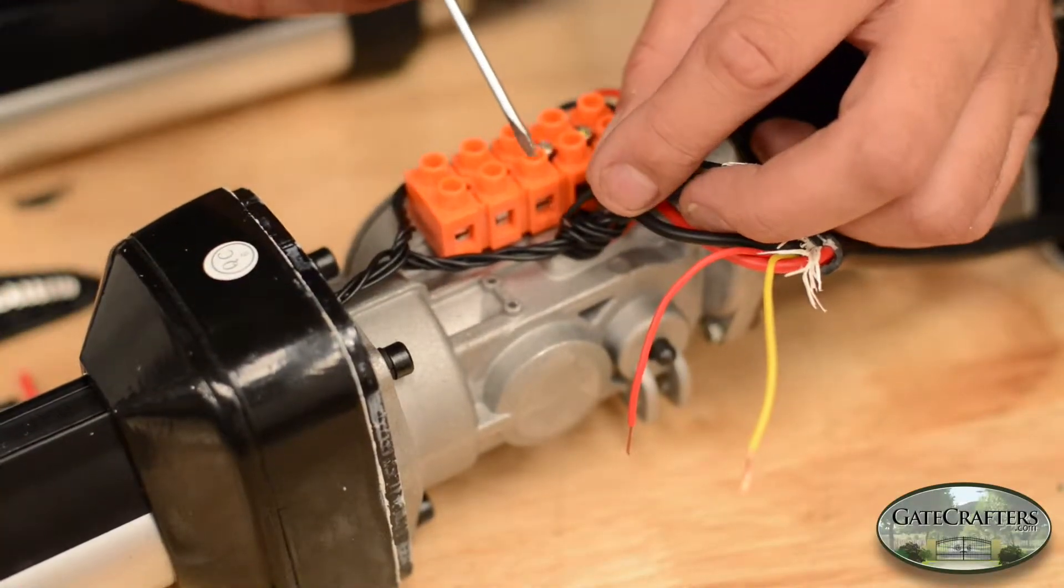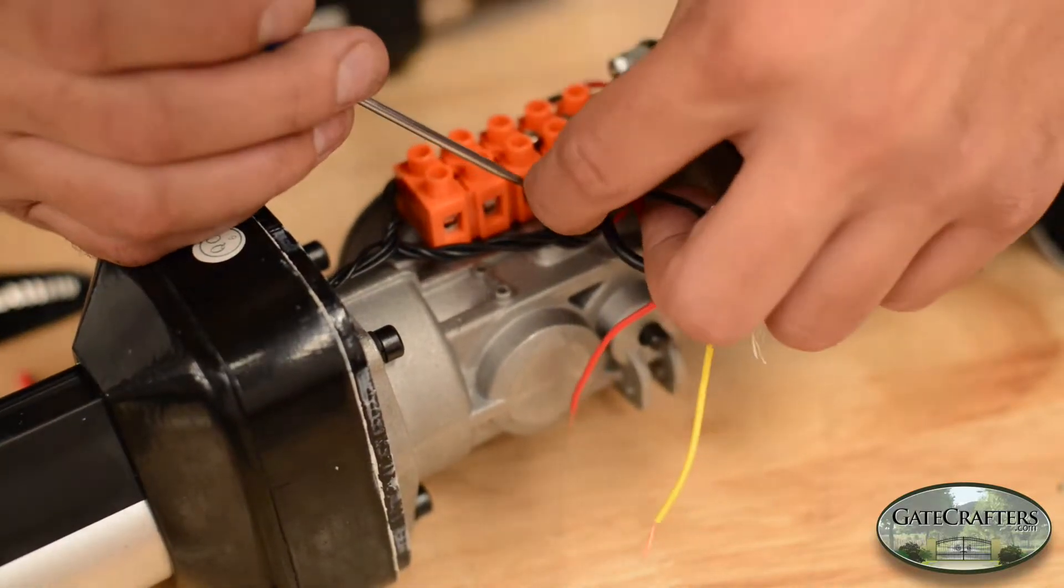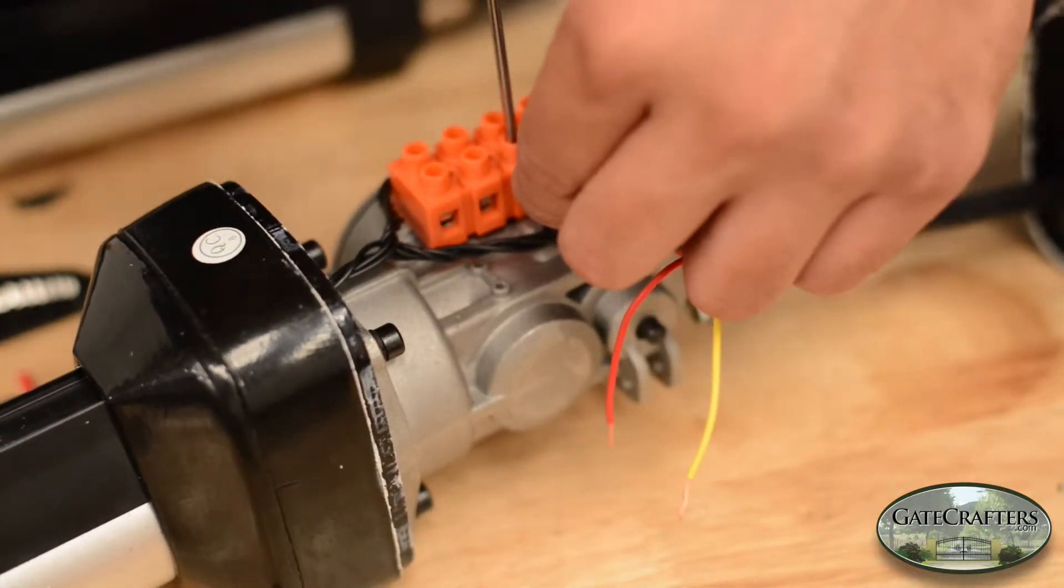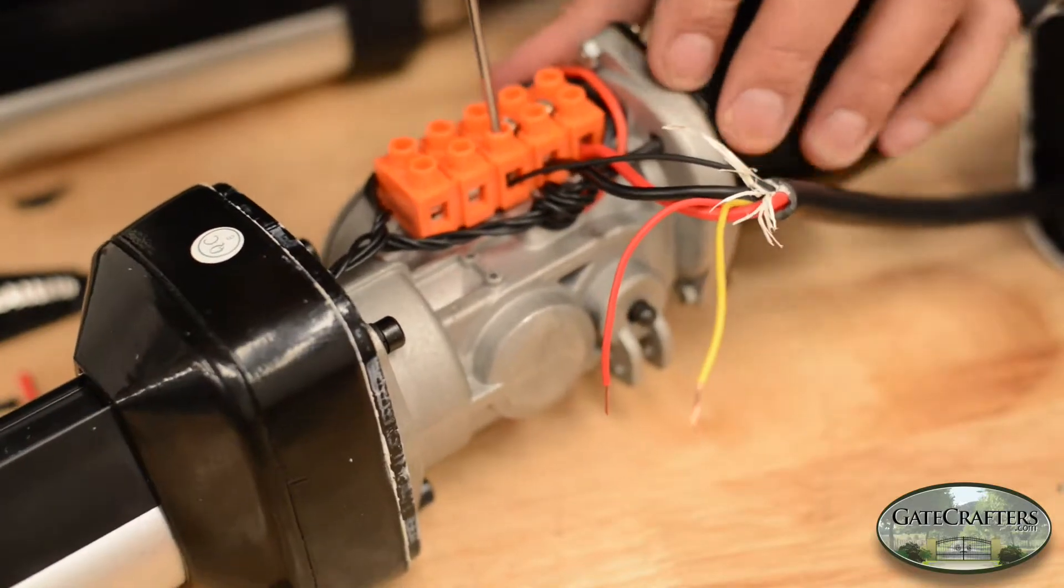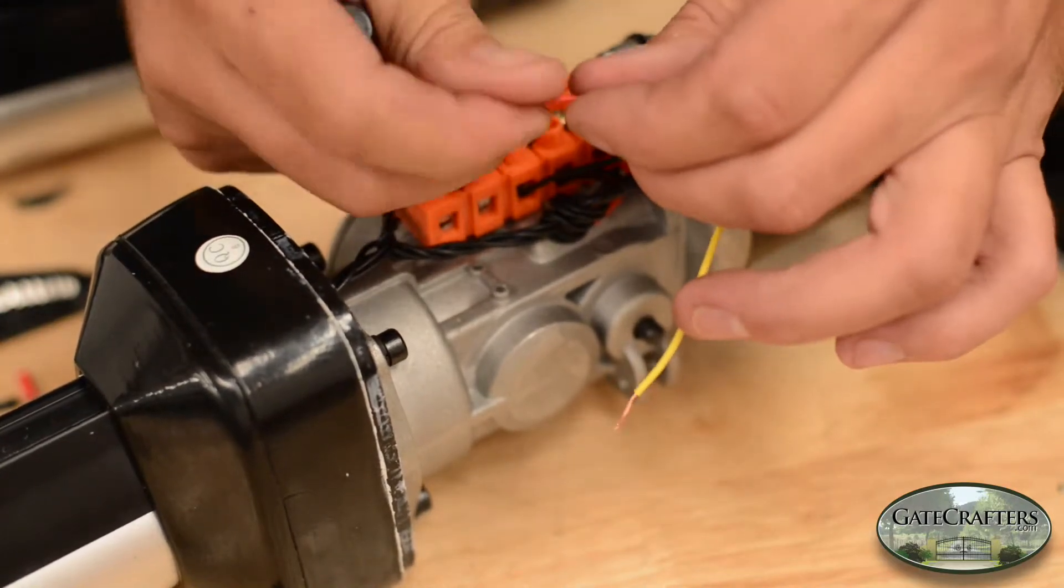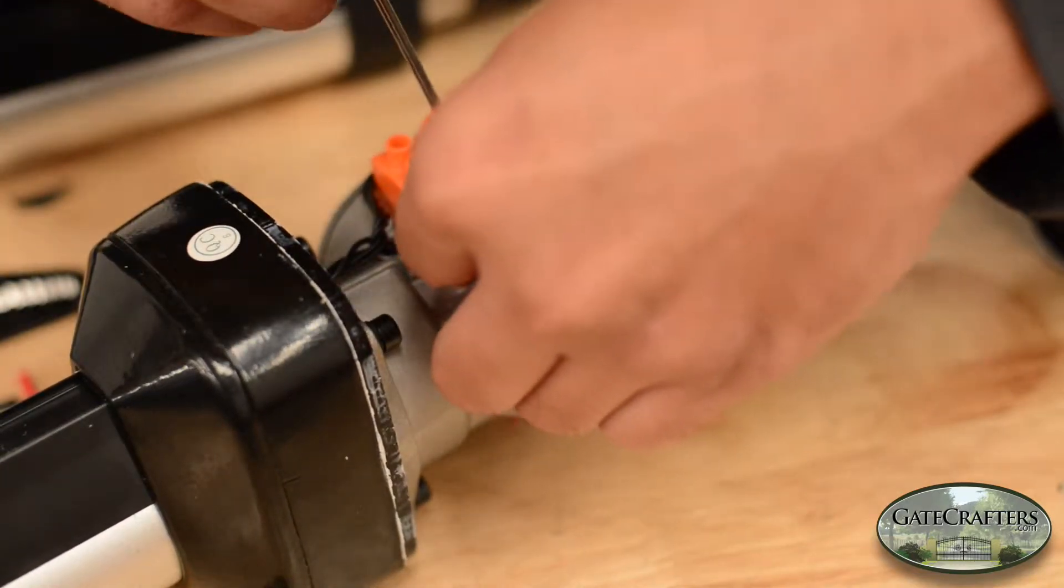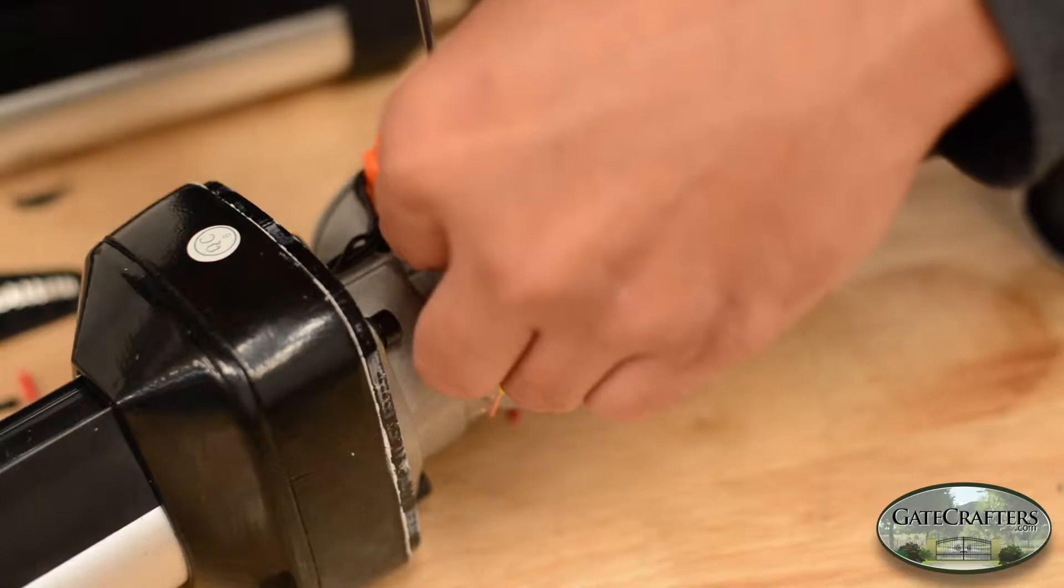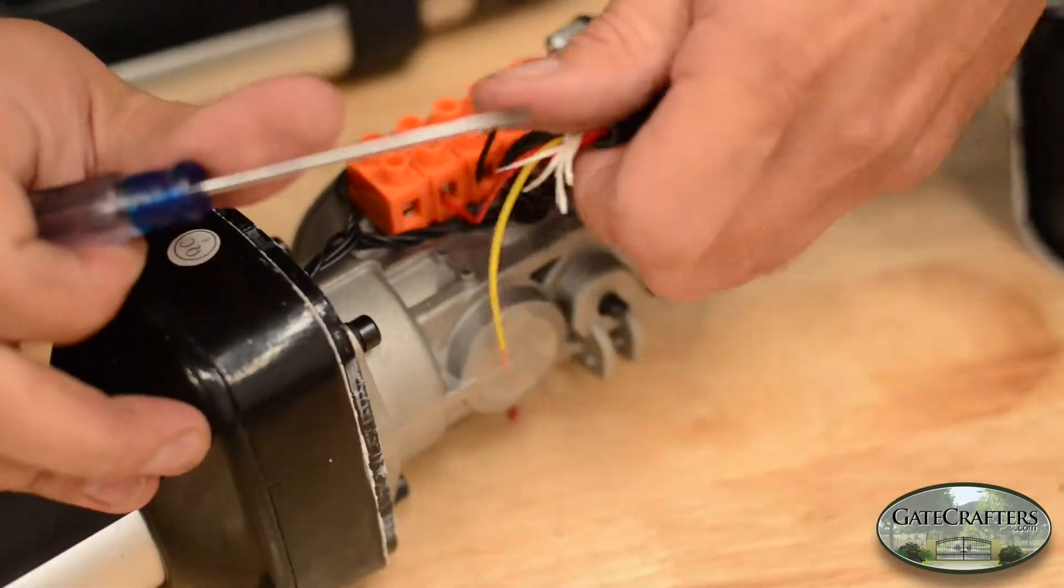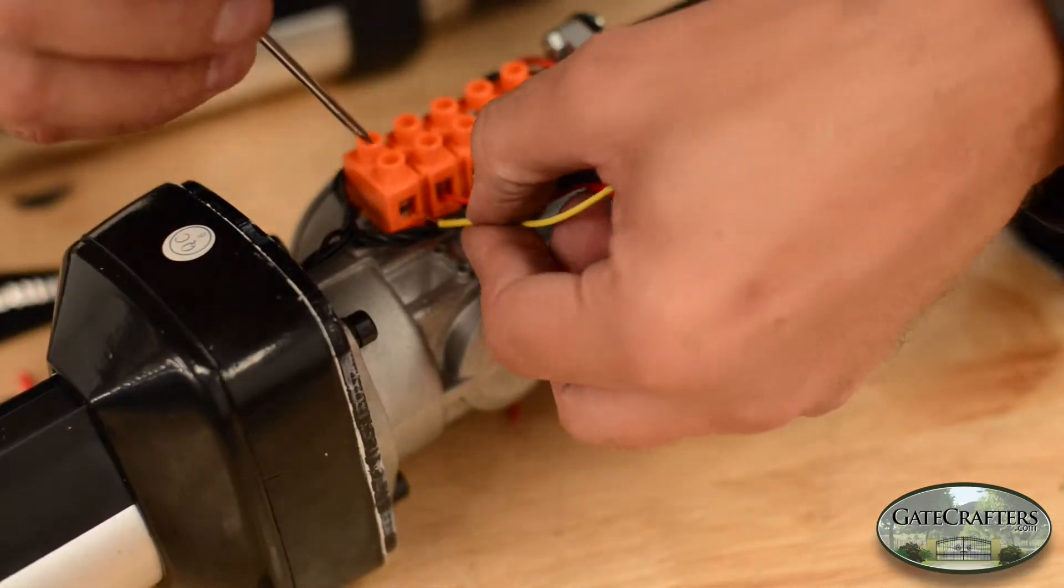Remember that they have to go in a specific order, so it has to go black, red, and then yellow. Red is your common, black is the extended limit. In most cases, that's the closed limit because the arm is extended while it's closed. So we'll put these wires in, and then we'll do a little check to make sure we did everything correctly. Remember to give a little tug on the wire, make sure you got a good connection, make sure it's making a metal to metal connection.